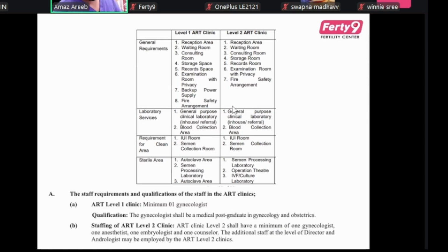And if you want a pathology lab, you can also have that. The IUI room, semen collection room, and andrology room should be adjacent to each other, where the collection will happen in one room, and thereby through the pass box it will be transferred to the andrology room where the processing will take place. From the andrology lab, there should be a pass box to the IUI room, with the labeling done and the name told loudly so the patient can recognize that their sample is being used.